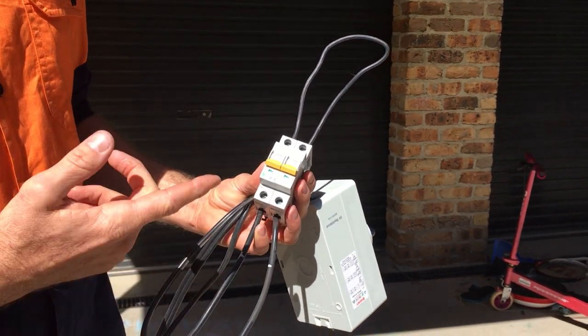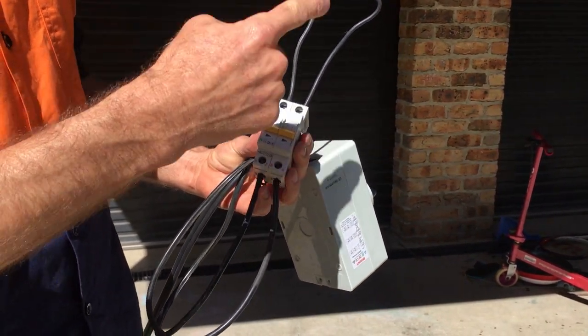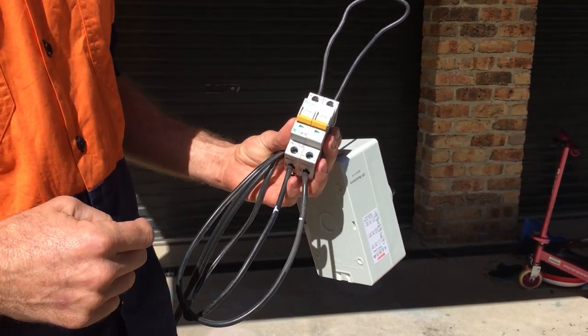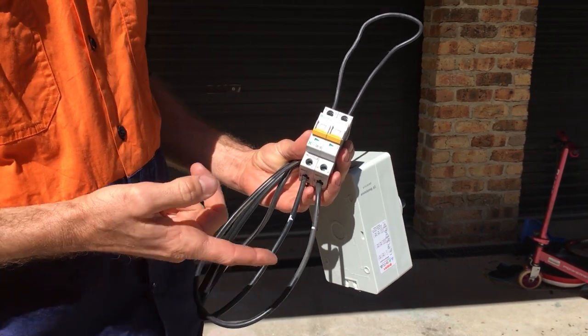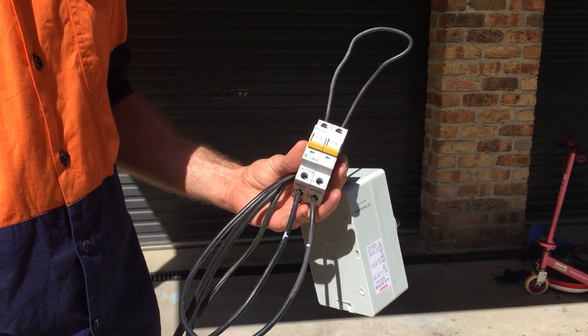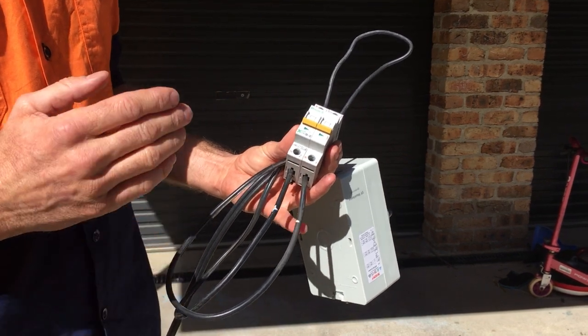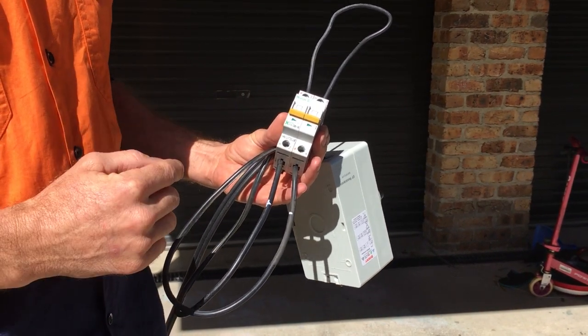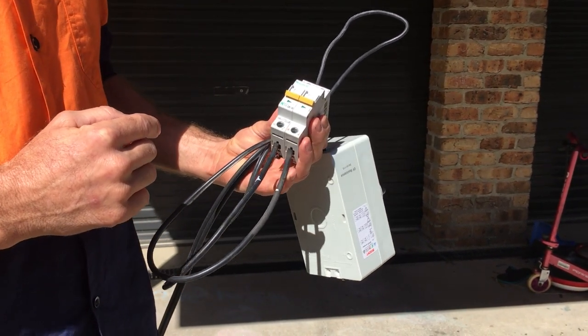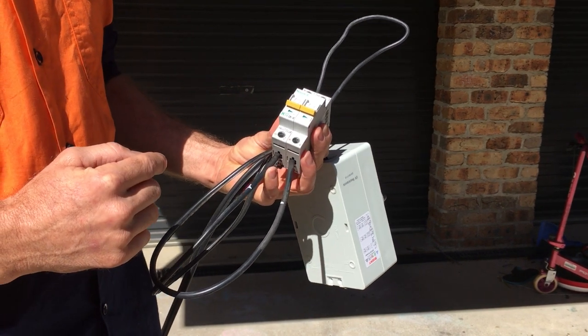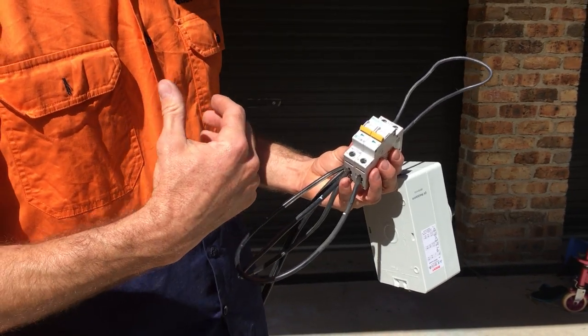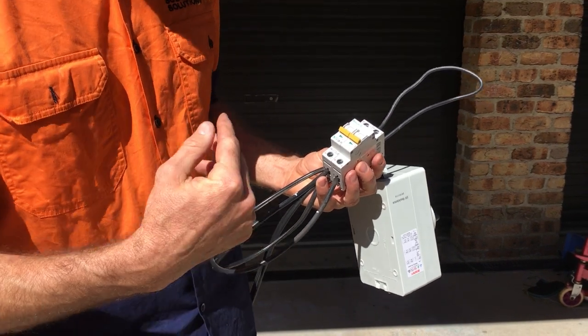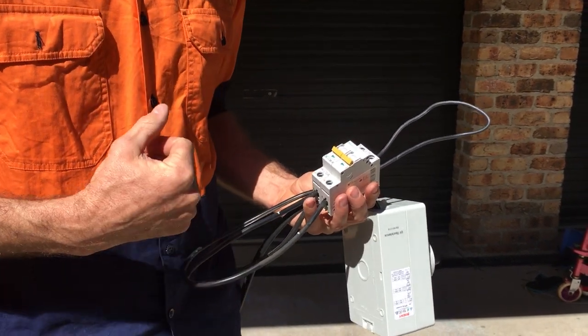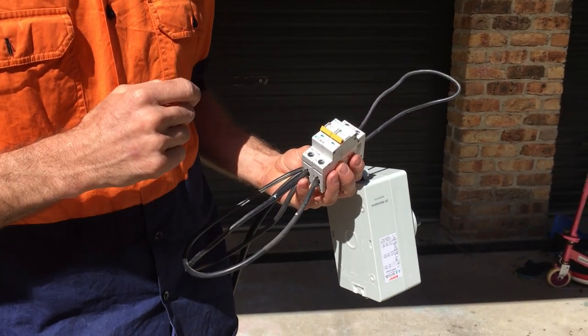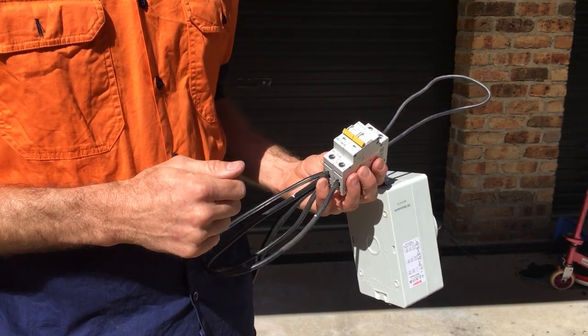So when I actually turn this on, it's going to have full current across it, full short circuit current from the solar panels. And when we turn it off, it's going to try and disconnect that. But the thing with these isolators is they are polarized isolators, and when they are wired in reverse, it's actually going to create an environment where the arc can continue. And so it causes these to have a major catastrophic failure.